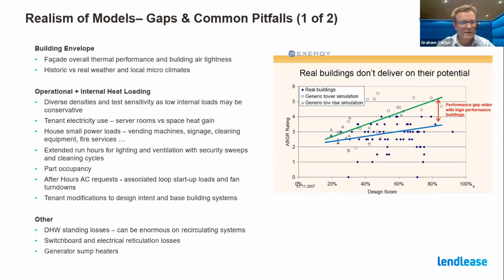We push electricity through wires and switchboards, and electrical consultants in Australia allow for 5% voltage drop. You might see about half of that on average. That's another 2.5%. It doesn't sound like a lot, but all these little things need to be accounted for and not just slid into the simulation margin all the time. And we actually learned some really hard lessons about generator sump heaters that have to keep the oil at a certain temperature. Again, not often thought about, but it's really important.